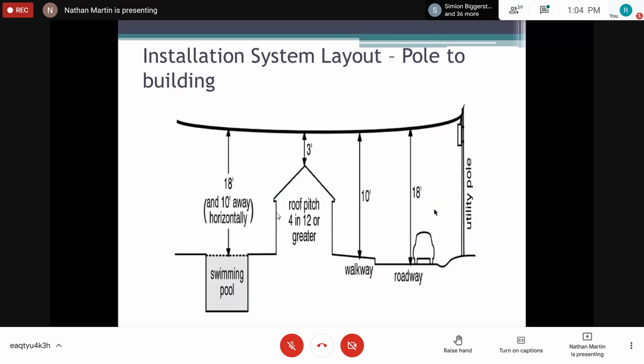All right, these are some clearance measurements for overhead service line. So if this is your utility pole, we're talking about a road where we should have a clearance of at least 18 feet, right? If we have a walkway, you realize that the walkway should have at least 10 feet clearance, and we must have a 3 feet clearance above any surface roof, and so on. So a swimming pool will still have 18, right, and 10 feet away horizontally.